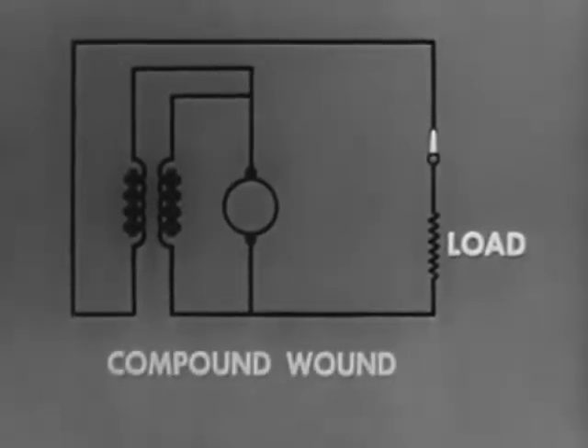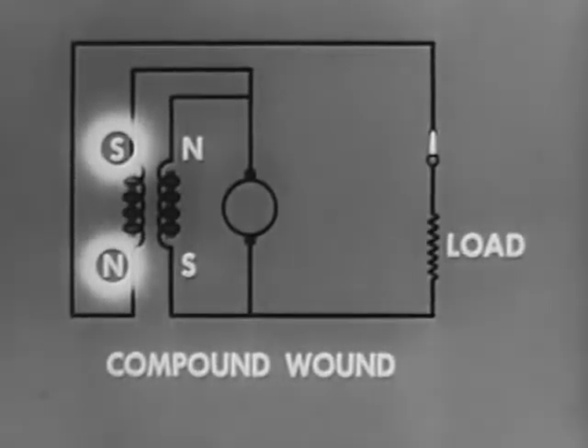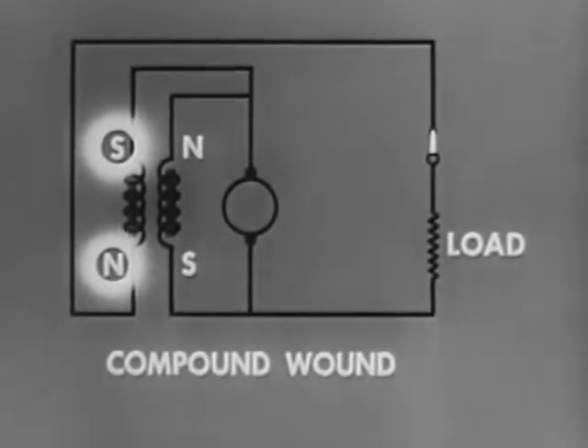By changing the field winding, a compound wound generator results, which combines the best features of both types — the series and the shunt wound generator. When windings are arranged so that magnetic fields oppose each other, it becomes, in effect, a series generator. This is used only where constant current is the prime requirement, such as in arc welding.